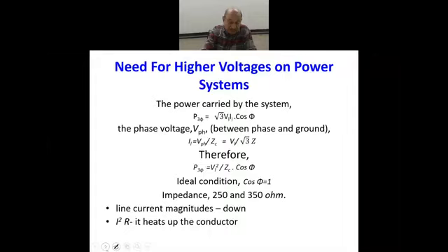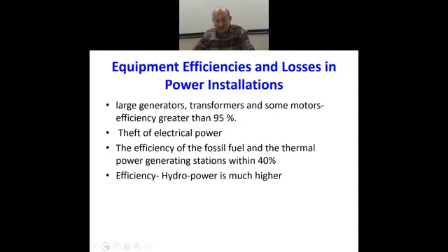If you want to increase the power handled by a transmission line, increase the voltage, and the power handling capability will increase tremendously. So it is not desirable to increase the line current, because the I square R losses, which get converted to heat in the conductor, are not desirable. And there is a tremendous power loss also.